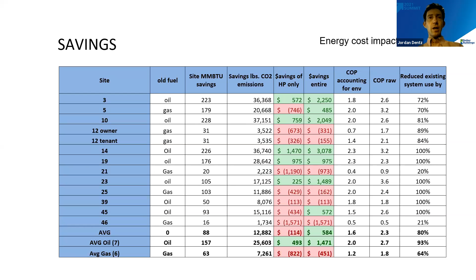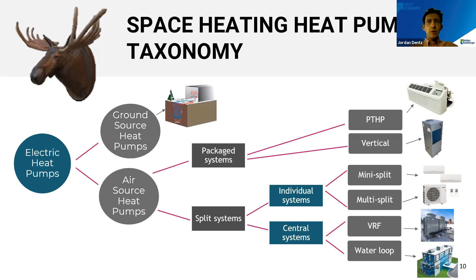I want to give an overview of space conditioning heat pumps and talk about some new technologies in the marketplace. We're focused strictly on electric heat pumps, particularly air source heat pumps—ground source heat pumps are appropriate in certain cases, but air source systems are generally easier and applicable to more buildings. Air source heat pumps can be divided into package systems, where the entire heat pump is in one box, versus split systems with separate outdoor and indoor units. Split systems can further be divided into large central systems serving an entire building, commonly called VRF systems, or individual systems like the mini-splits we installed in the previous project, with anywhere from one to a handful of indoor units connected to each outdoor unit.